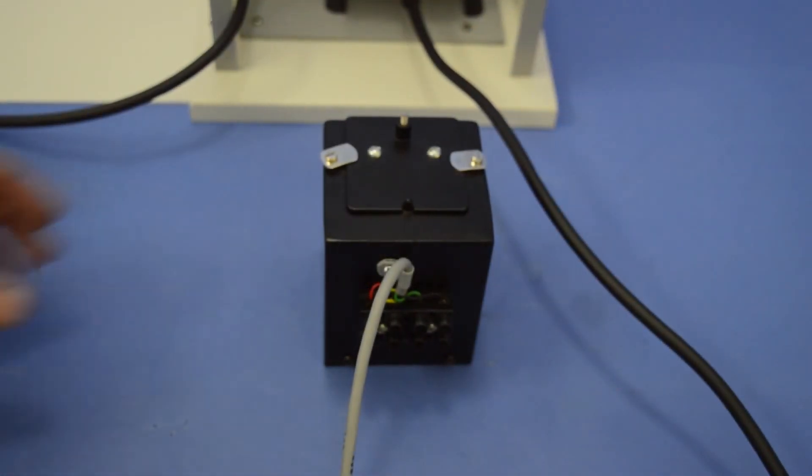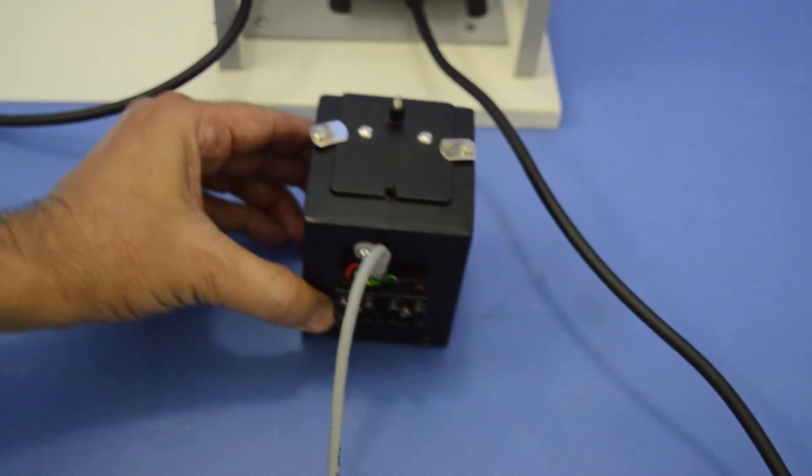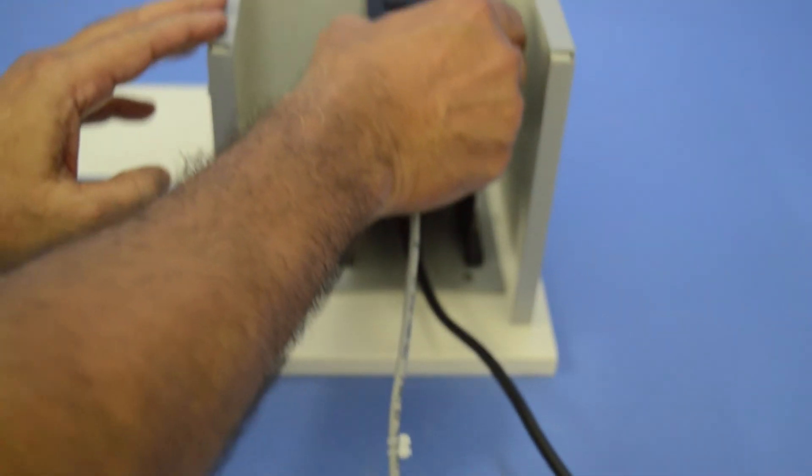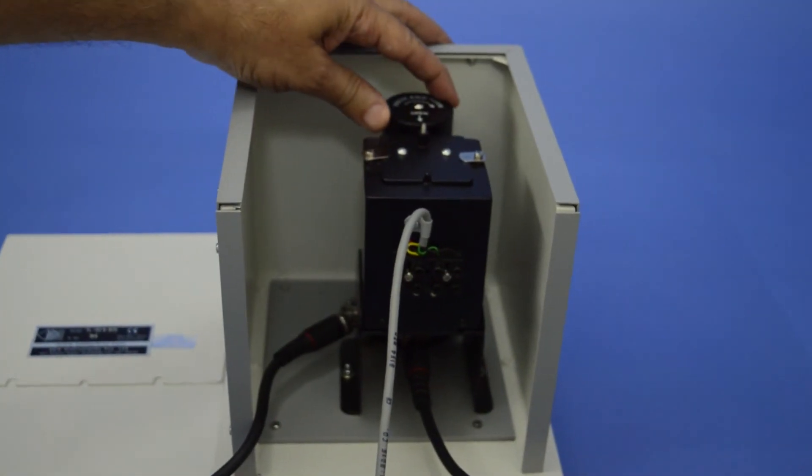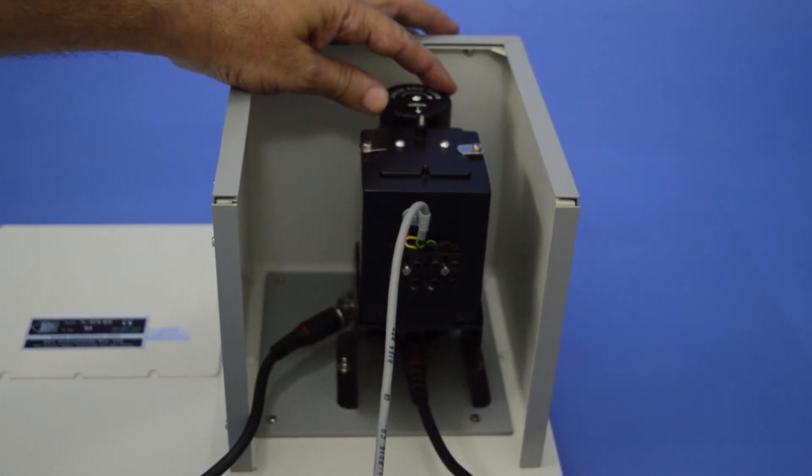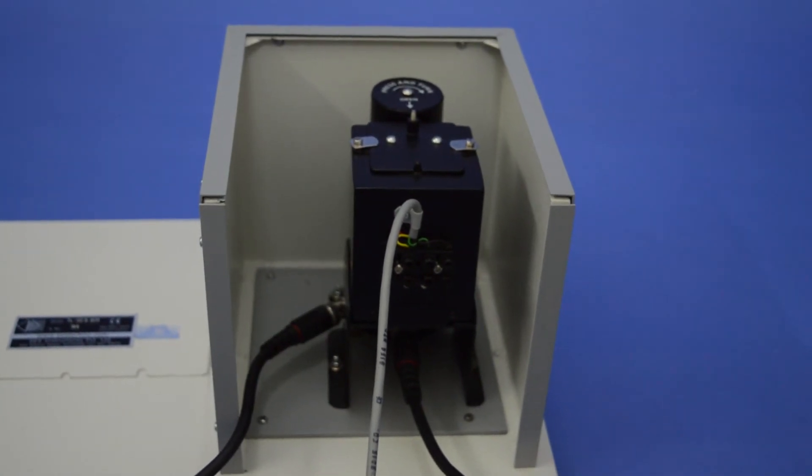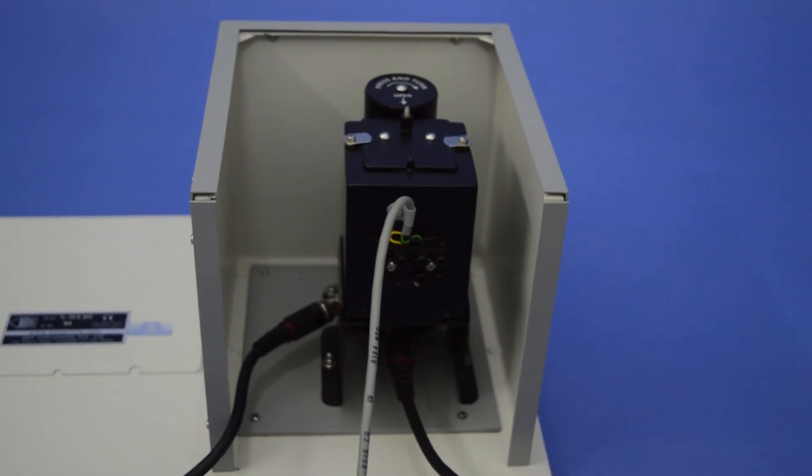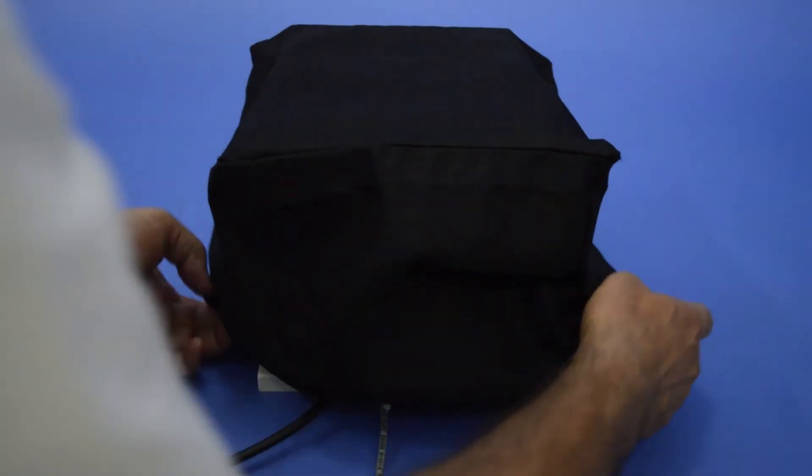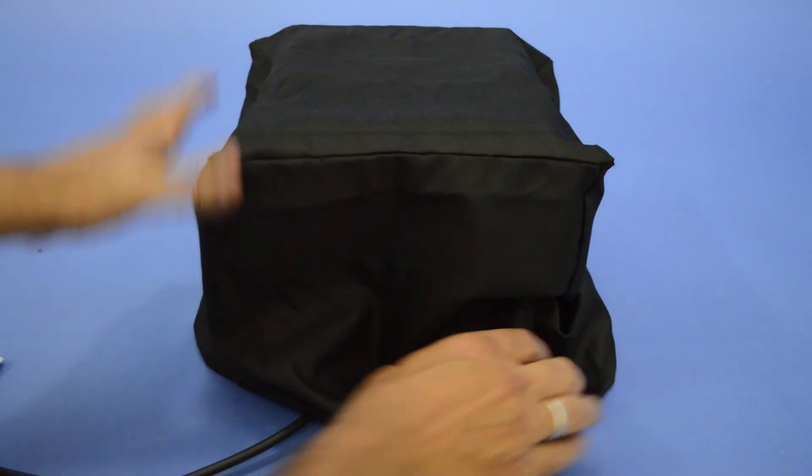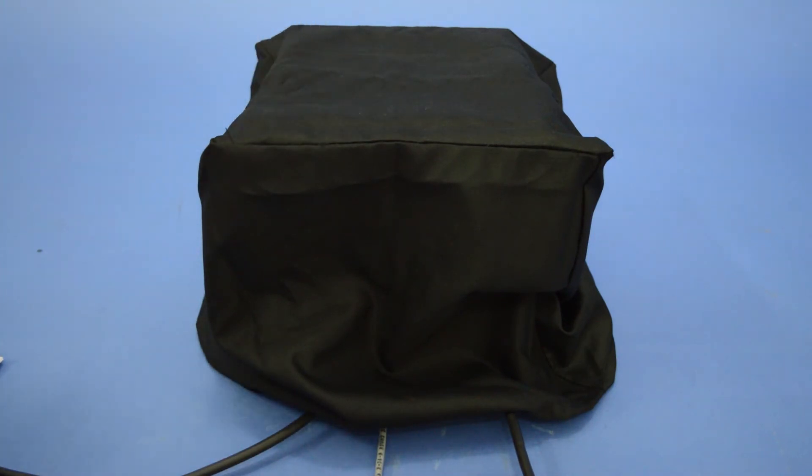Now put it back on its own stand and open the PMT housing window and ensure that the flat face of the crystal faces the PMT window. Now close the black box and cover it with black cover. This will protect the PMT tube from stray light.